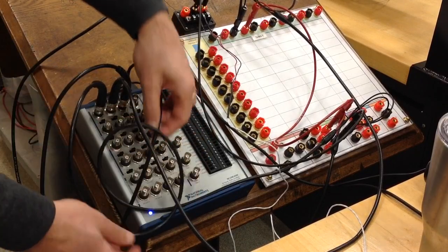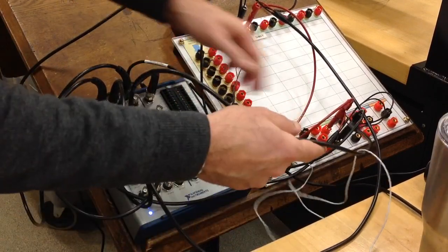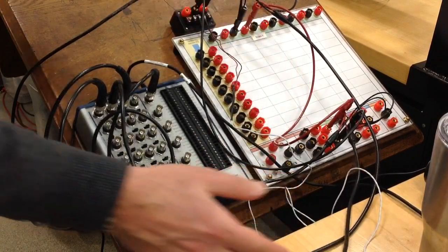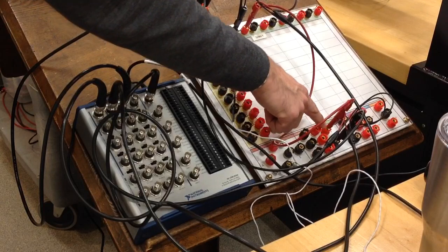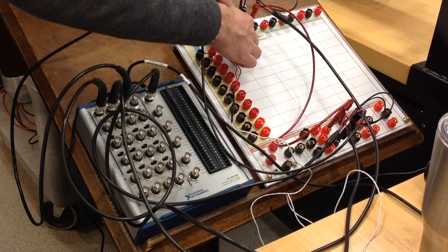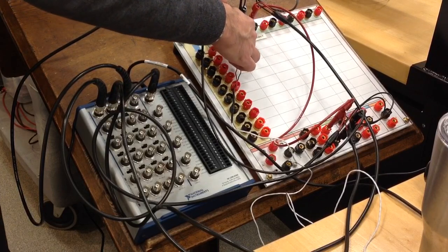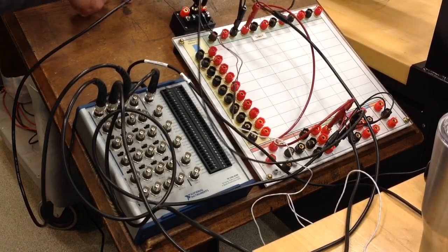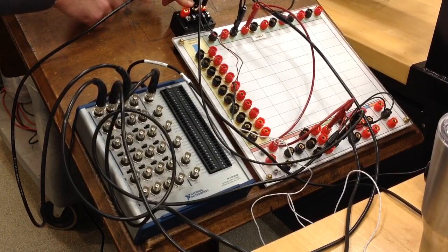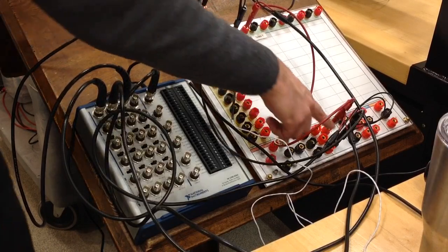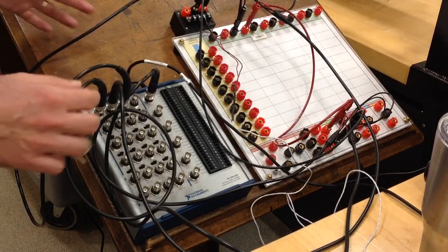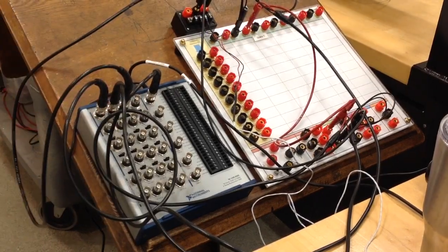So I have an analog output here. So this cable provides the excitation voltage at the power terminals here. And power goes from the positive side to the positive side of the reference resistor. And from the negative side of the reference resistor, I have a connection to the connectivity plate. And then finally, from the negative side of the connectivity plate, I have a connection to the negative terminal of the power terminals.